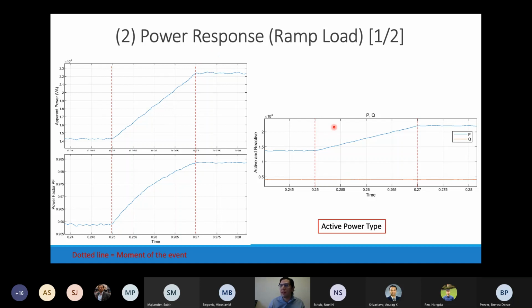So as we can see, this is an entirely resistive load, which is adding just active power. A critical point here is to notice that the grid already has load introduced to it. That's the reason why it's not at 0, unlike the previous slide that I showed. So here we are basically adding a new type of load, which is a traditional type of operation. As we know, we keep adding and removing loads basically all the time. So we can see how the inverter responds to this type of load and how it settles down until it reaches the maximum point.